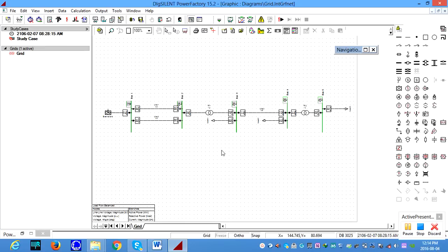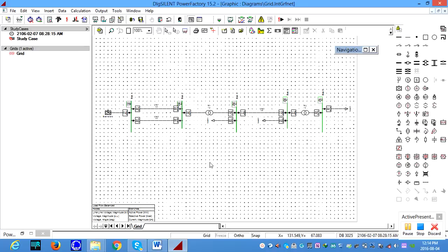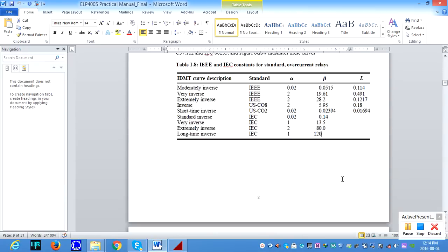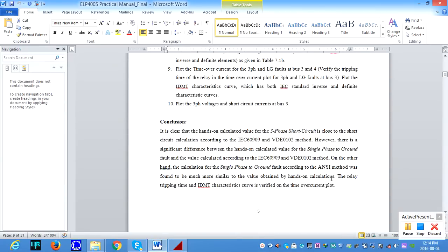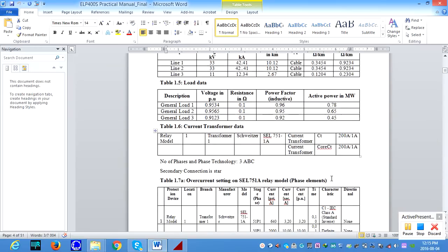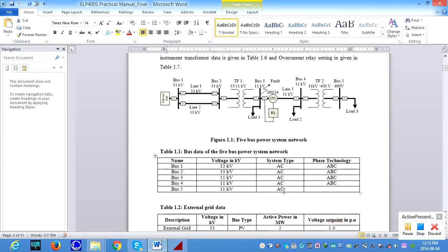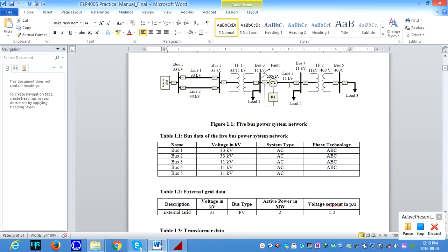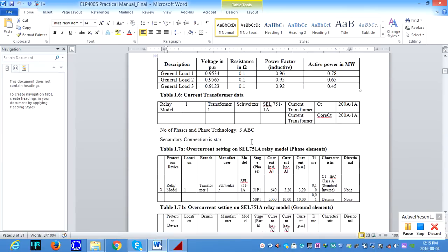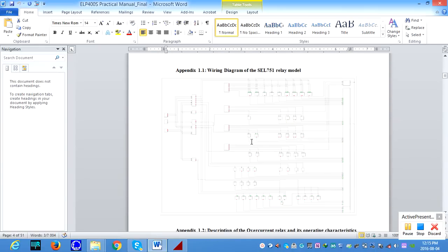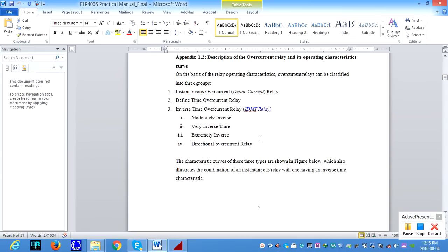Now we need to move on to the next part of the exercise, that is basically your protection setting. For the protection settings, first we are trying to give the overcurrent protection that we need to use. If you look at the single line diagram, we need to insert your current transformers and the overcurrent relay model, which is close to bus 3, and verify the protection setting for this scenario. Okay, and as part of the manual, we also explained the description of the overcurrent relay and the operating characteristics.